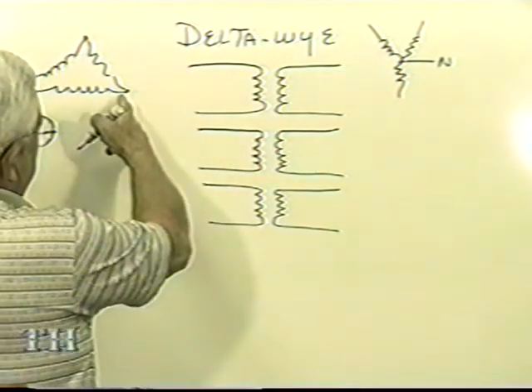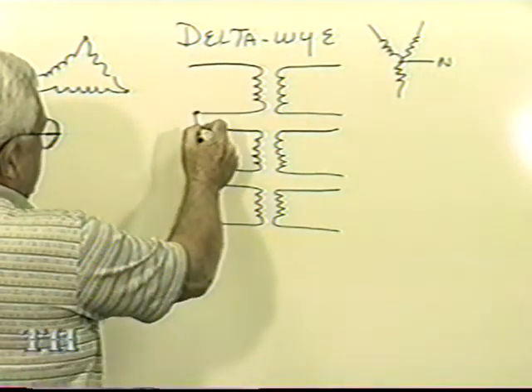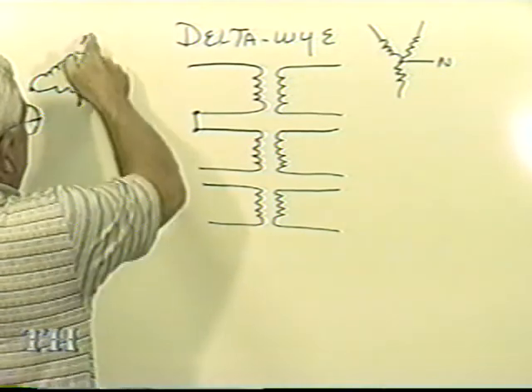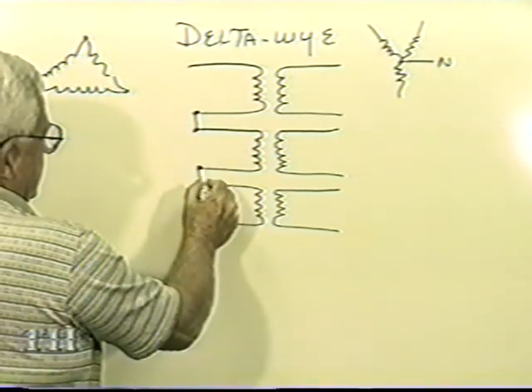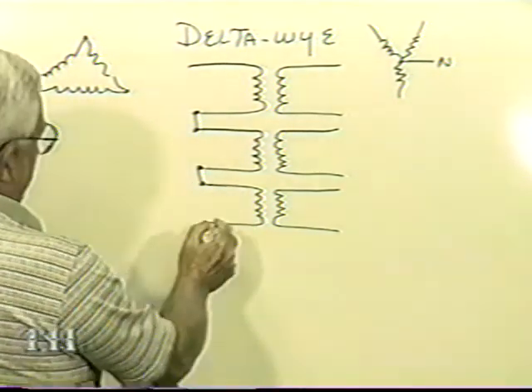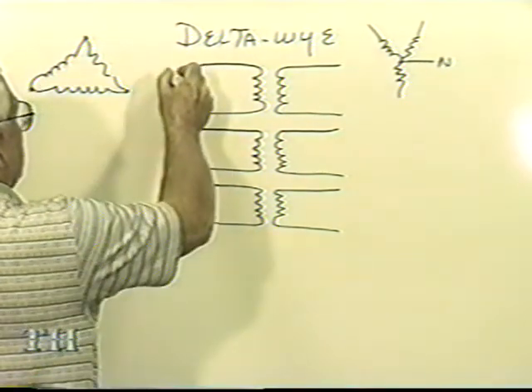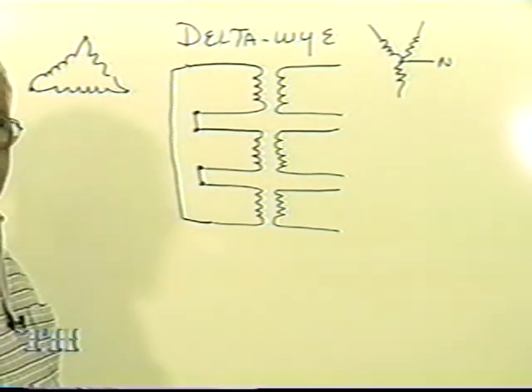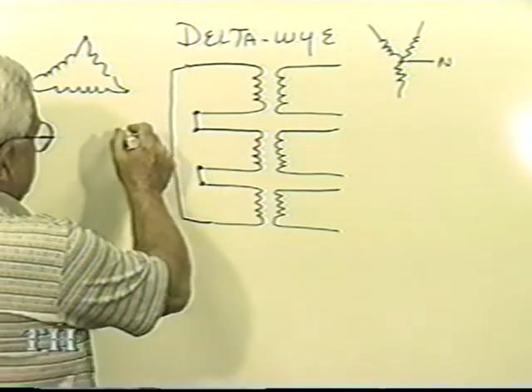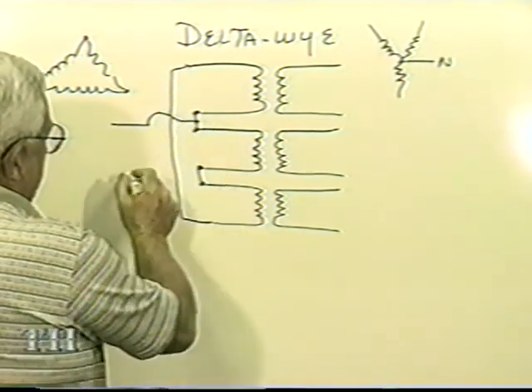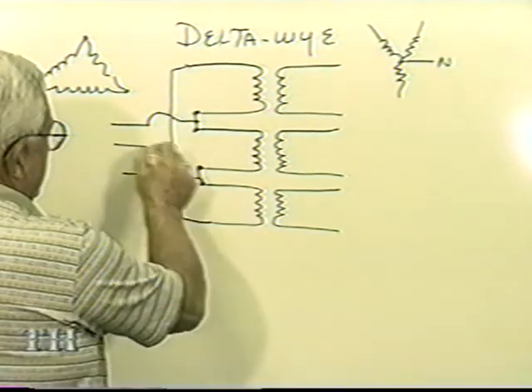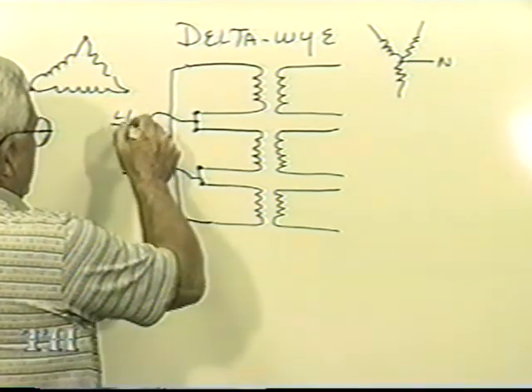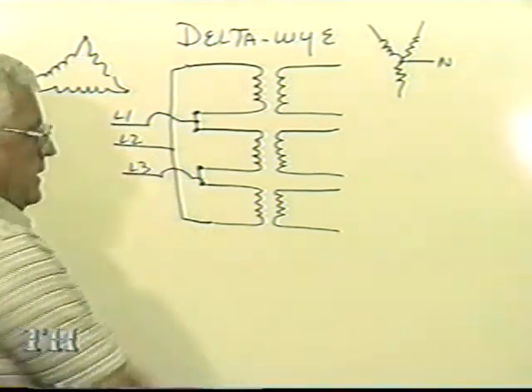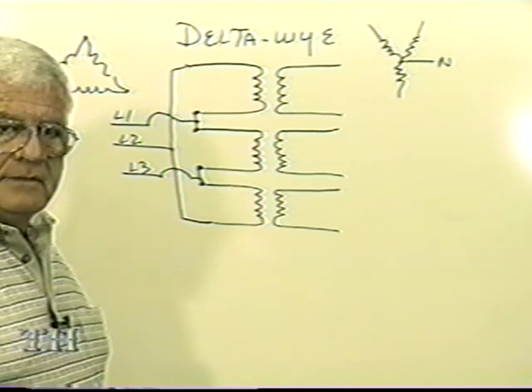Watch: if I was to connect this, I would take these 2 coils and connect them together. I come up here and take these 2 coils and connect them together. Then I have to come from here, up here, and make my connection. All I'd have to do is come in here with a line wire, here with a line wire, and here, going L1, L2, L3. That's how my delta would connect.